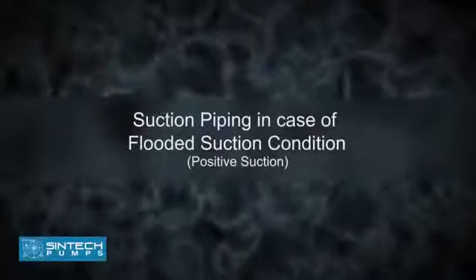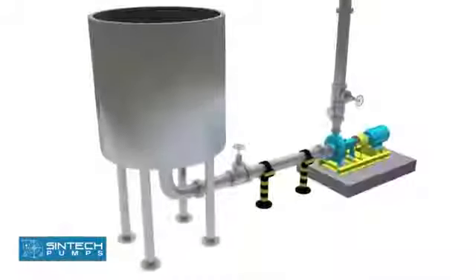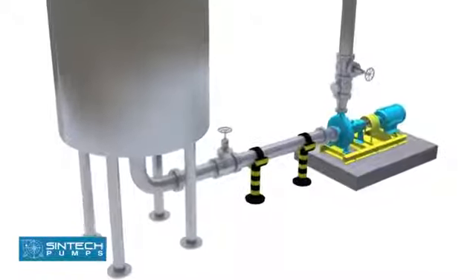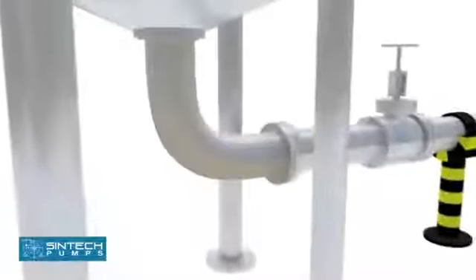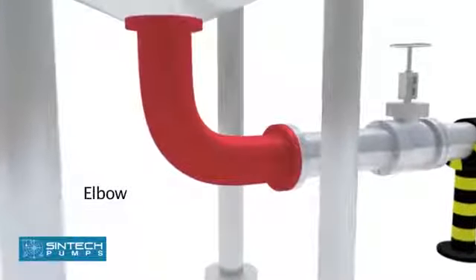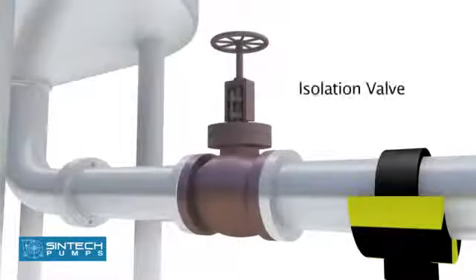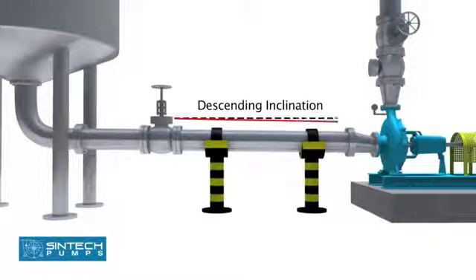Suction piping in case of flooded suction condition (positive suction): In case water is being supplied to the suction through gravity, for example an overhead tank, a slightly different setup is needed. The elbow should be of standard type or long radius type. An isolation valve should be provided in the suction line. The pipe supplying from the tank into the pump should have a descending inclination.